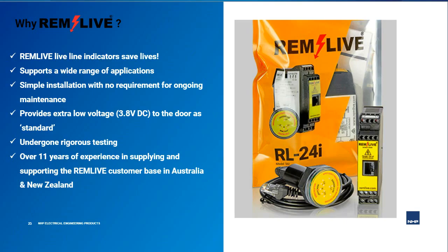So why select the REMLIVE Live Line Indicator? With its use in the isolation verification process, the REMLIVE Live Line Indicator can help prevent electrical accidents from occurring and ultimately saves lives. It supports a wide range of applications as a single device type. We covered before the various wiring configurations that it has, and its ability now to monitor voltages up to 1000 volts. The components included for this product easily connect together and are very simple to install on the panel. It doesn't require any ongoing maintenance.